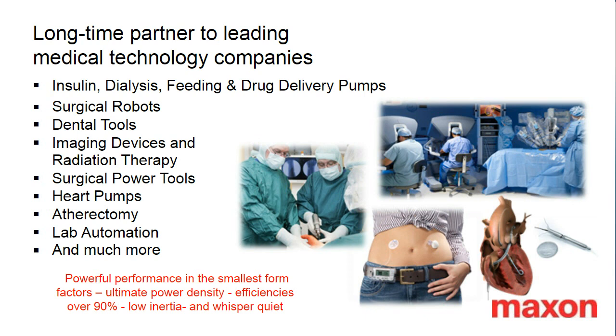And related to the pictures, where you have an insulin pump, the motor must dose insulin correctly every 3 minutes. And if this drive runs too fast or too slow or fails to function, you can see that's going to cause a serious problem for the diabetic that's wearing it. So again, critical to function, must work. This is where Maxon plays.